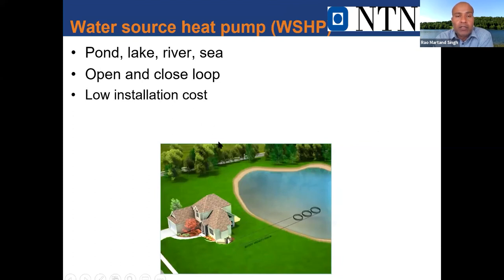Another type of system uses a lake or pond. If you have a house near a lake, pond, river, or sea, loops can be placed there. It's a very low-cost system because there's no drilling, just placing the loops, and the loops themselves are not expensive - they are plastic pipes, very cheap. So if you live near a water body, that can be utilized. Water works the same way as the ground: water temperature after 2-3 meters remains the same, it doesn't change throughout the year.